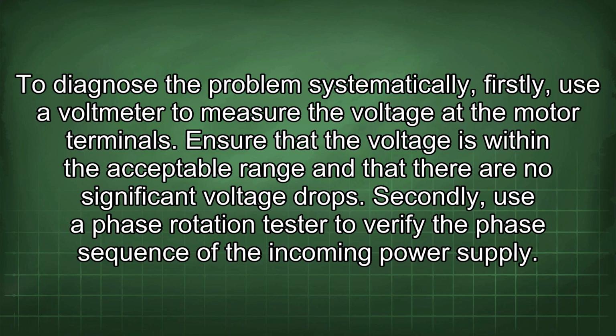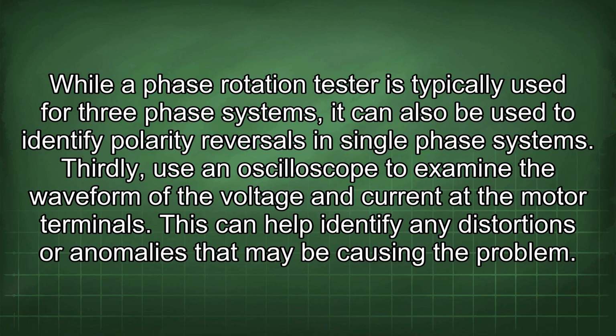Ensure that the voltage is within the acceptable range and that there are no significant voltage drops. Secondly, use a phase rotation tester to verify the phase sequence of the incoming power supply. While a phase rotation tester is typically used for three-phase systems, it can also be used to identify polarity reversals in single-phase systems. Thirdly, use an oscilloscope to examine the waveform of the voltage and currents at the motor terminals. This can help identify any distortions or anomalies that may be causing the problem.